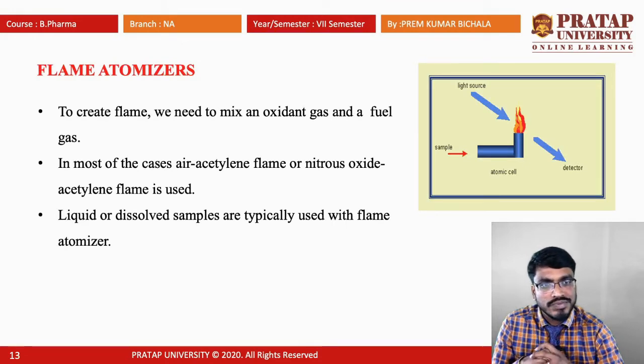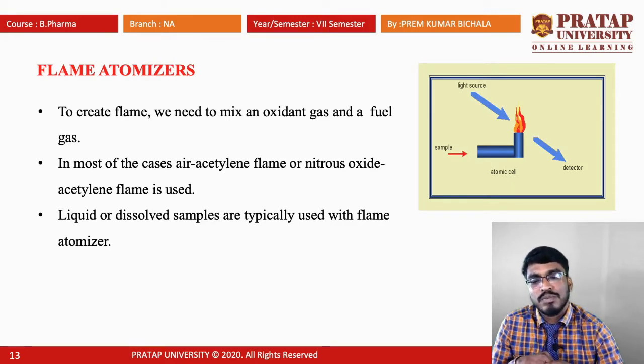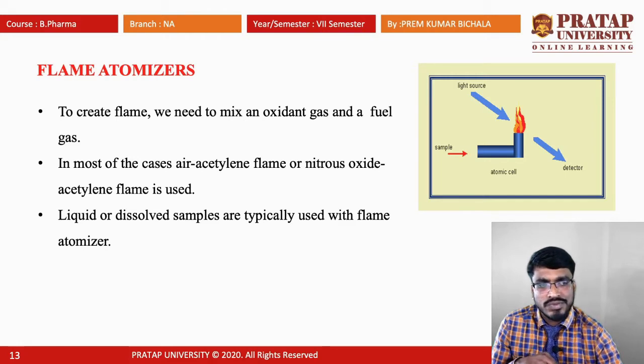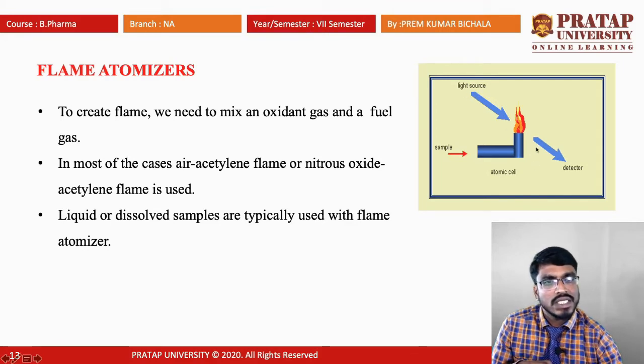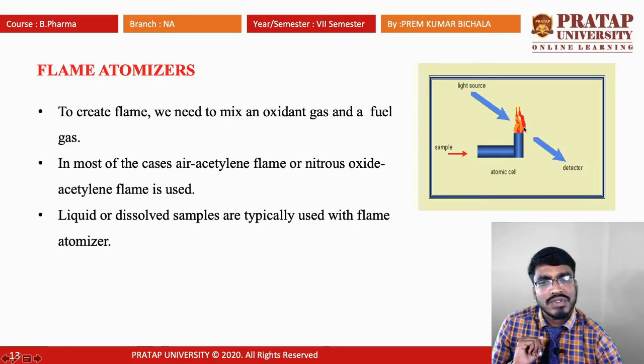The flame atomizer is mainly used to create a flame. We need to mix an oxidant gas and a fuel gas. In most cases, an air-acetylene flame or nitrous oxide-acetylene flame is used. Sometimes liquid or dissolved samples are also used with flame atomizers. Here the hollow cathode lamp is the light source. The sample vaporizes and then moves to the atomic cell where it produces a gas flame. The light passes through the flame where we have the excited sample cell, and that signal travels to the detectors.